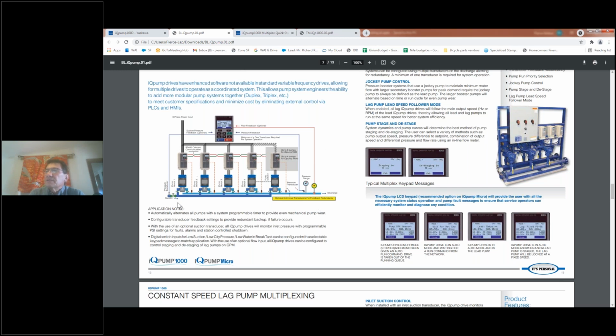So this is a multiplex system. And what it involves is a lot of extra piping, a lot of extra hardware, a lot of extra wiring. But what you get is a remarkably reliable system. The multiplex system also gives you redundancy in the mechanically driven equipment, which is the pumps. So, in the case of, let's just take the 4 200s here and ignore this one, but you can do up to 8. In this case, we have an 800 horsepower sizing.